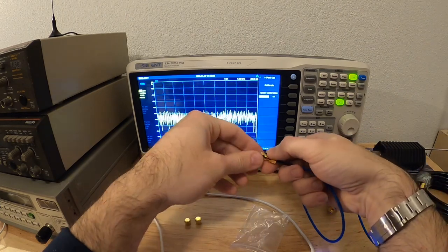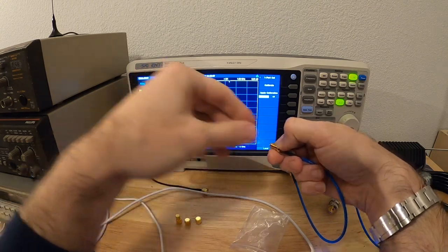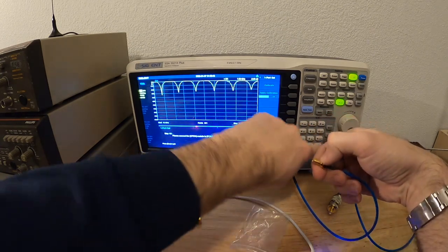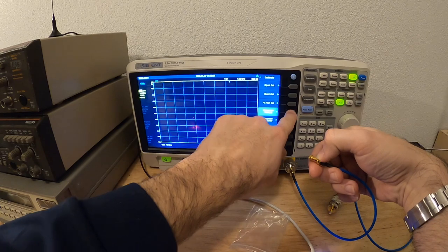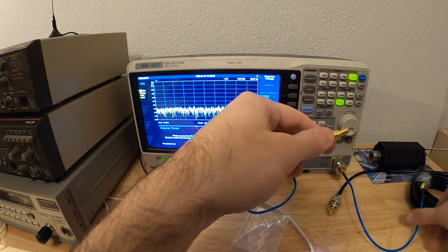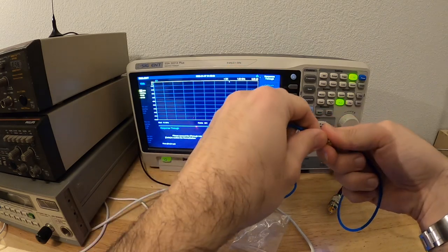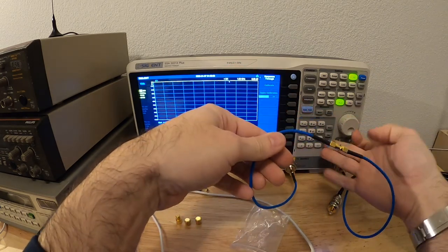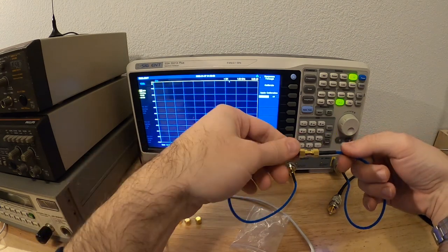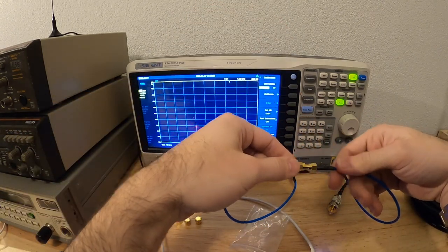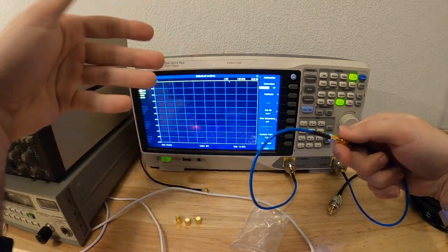All right. So this is done. But since I'm also going later on to do a transmission measurement, S21, I'm also going to calibrate for that. I go to through, and I do calibrate. And I just connect them together, just like that. And then press enter. Press enter. All right. It's calibrated completely. Perfect. So I just go back. And we are good. So I'm just going to repeat that on the other VNAs.